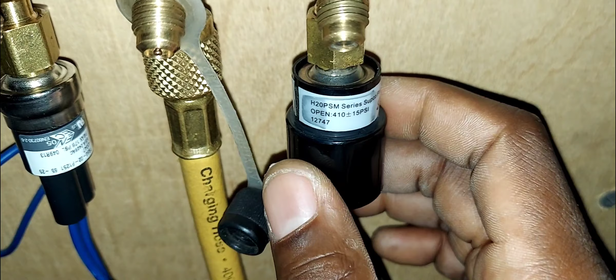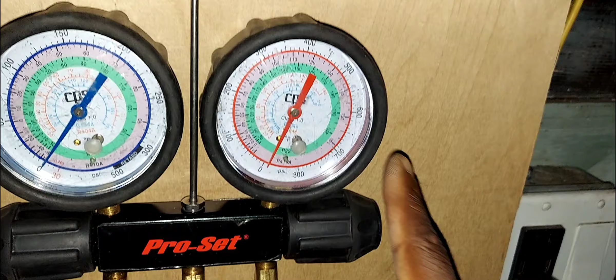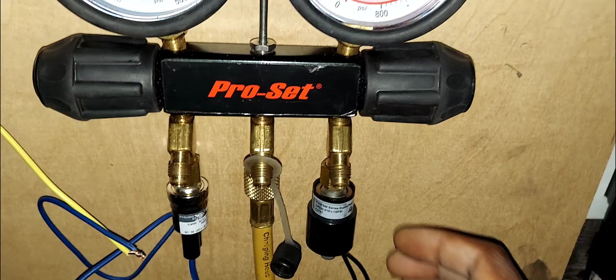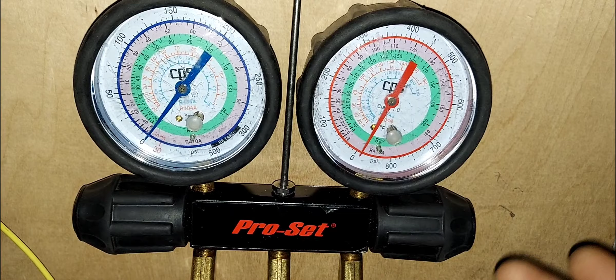On the opposite side, this switch right here is a normally closed switch, so it's going to be closed at all times except when the pressure is above 410 psi, and there's a plus or minus 15 psi accuracy. The rating on this is 410, and with a 410 psi safety cutoff, this is definitely going to be an R22 switch as well, because if it was for R410A, it would be 500 or maybe 610, something like that. I think so. All right, you can comment in the comment section if you know exactly. But typically in an R410A system, the cutoff pressure would be at least 500 for a water cooled system, and if it's air cooled, it will be like 610 psi.